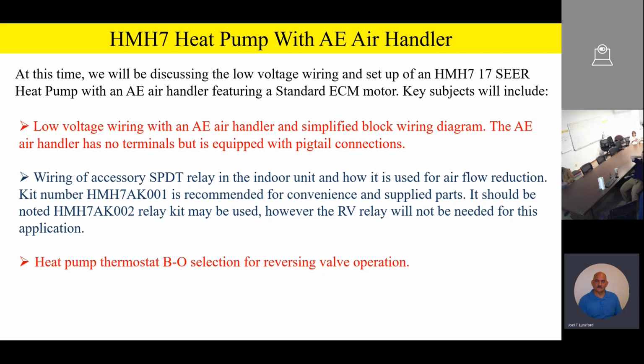We're going to talk about the low voltage wiring with an AE air handler and some simplified block wiring diagrams. We're going to be literally taking it from the thermostat to the indoor unit to the outdoor unit. Please remember, the air handler does not have terminals but is equipped with pigtail connections. On the block diagrams, I show a block where we're hooking up those low voltage terminals, but please remember they don't have physical terminals on the air handler, they are pigtail connections.